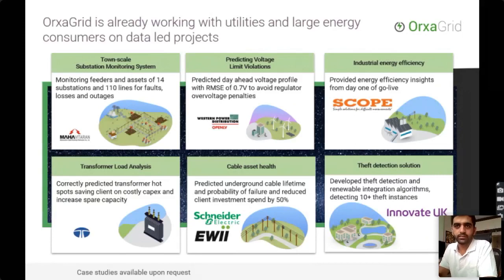On the data center, we installed the software application and ran various analytics to inform the grid operators, testing engineers, the O&M and circuit managers, to understand every time a fault was happening on the line. Instant SMS alerts were provided. If there were increasing losses within a transformer, certain transformers were identified as providing higher losses during energy transformation. We also identified battery banks that were fluctuating and required replacement or maintenance, and provided overall reporting tools to understand whether load shedding was happening as per plan, or whether there was excessive load shedding outside of the planned schedule. This was the Mahavitaran substation monitoring project.